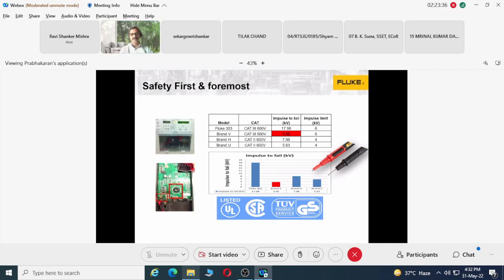Is this applicable only for DMMs or for all types of meters? It's applicable to all kinds of measuring devices used in electrical systems—it can be a multimeter, a clamp meter, a power analyzer. Sometimes an insulation tester also classifies, but it's not mandatory to have this category rating because you're not measuring voltage there, you're measuring resistance. But for other measurements, if you're measuring voltage and current, you definitely need it.